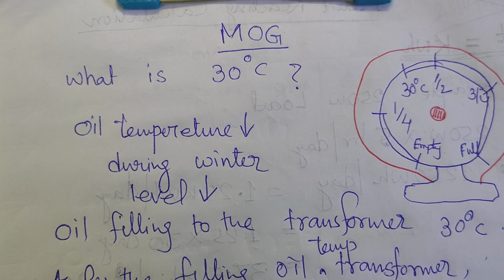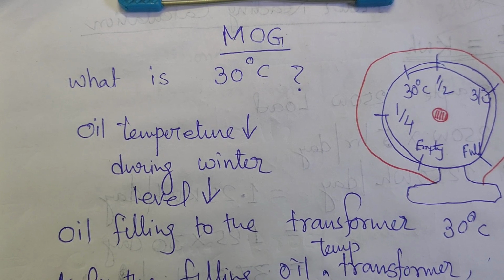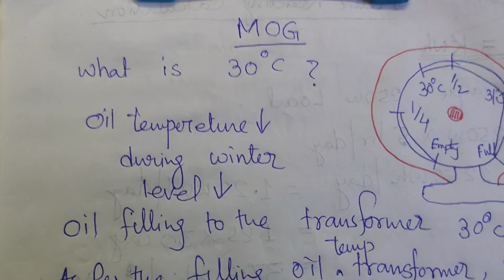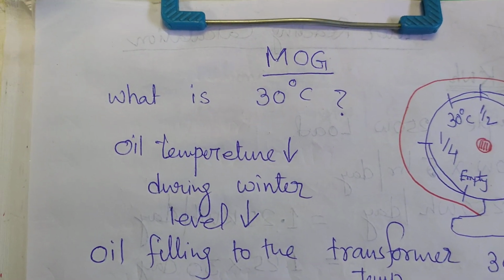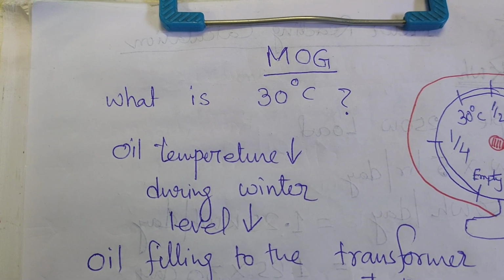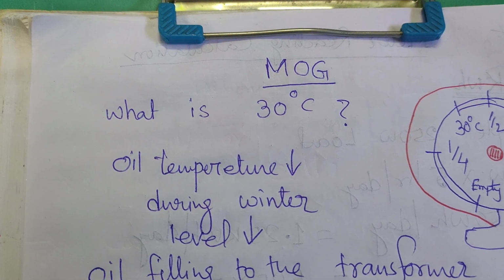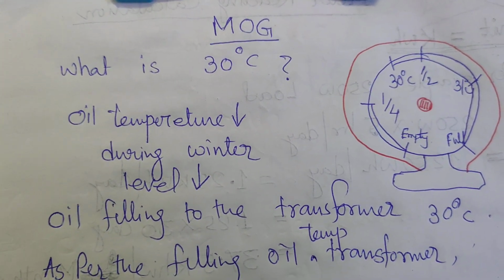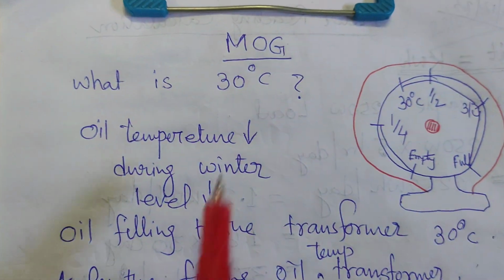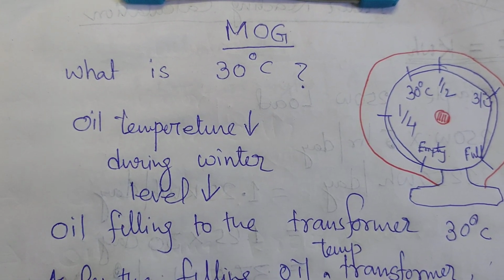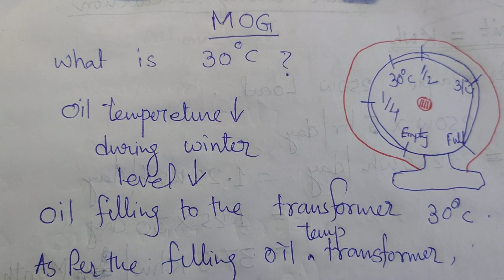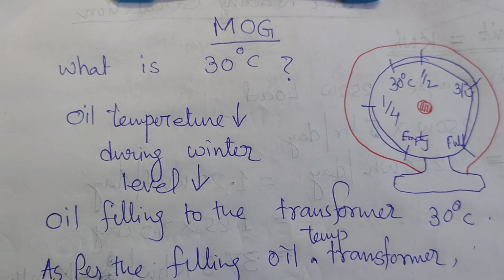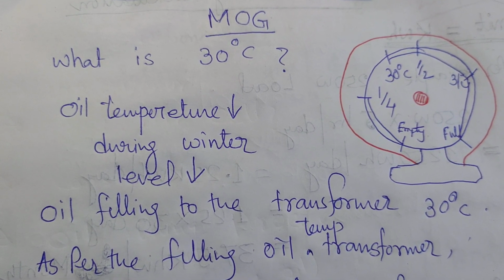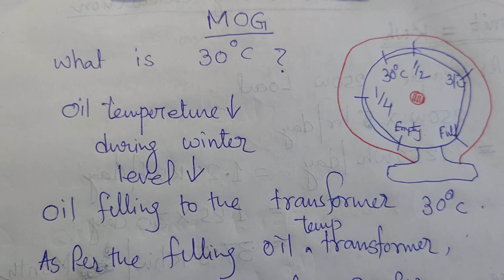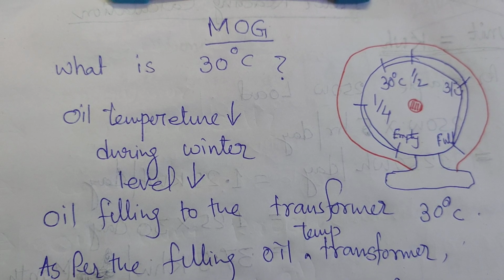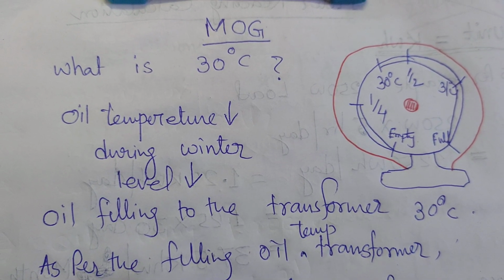Okay, thank you. Today my topic is the magnetic oil gauge. So why is it called magnetic? Because with the help of magnetic effects, it just rotates, and it is attached to the conservator of the transformers. And this gauge is very important for identifying and monitoring the oil level inside the conservators, and depending on the monitoring, checking and maintenance, we can smoothly operate our transformers without any problems.